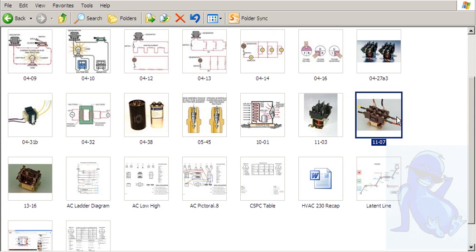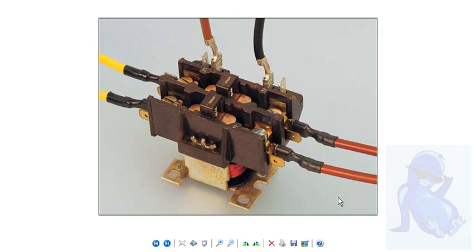What does a contactor look like? Voila, there's a contactor. Here's the low voltage leads that are hooked up right there, the 24 volts. When they are energized, this pulls down, that pulls down, and it allows current to pass through. That's high voltage current. So there's the low voltage coil, which is your load. That's where the resistance is for the low voltage circuit. On the high voltage side, the contactor is a switch. So this device right here is both a load on the bottom and a switch for high voltage to pass through. You literally have 2 circuits being worked or run through this device.